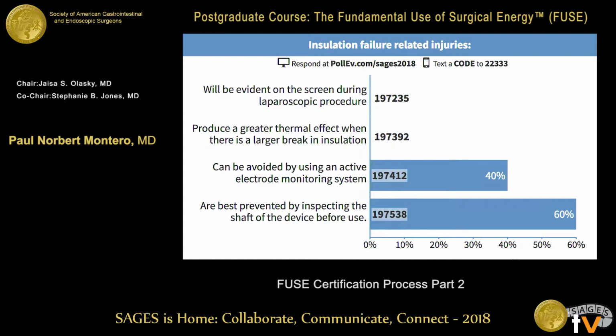They can be avoided by using an active electrode system, and there is a company that actually creates instruments that have an active electrode system, and that absorbs any stray currents that can come through. It is certainly in the insulated devices, but that has a way to withdraw any stray current through the system itself through an active electrode. They are not best prevented by inspecting the shaft of the device because it's the smaller holes that create a larger problem in the insulation, and you won't be able to see those.